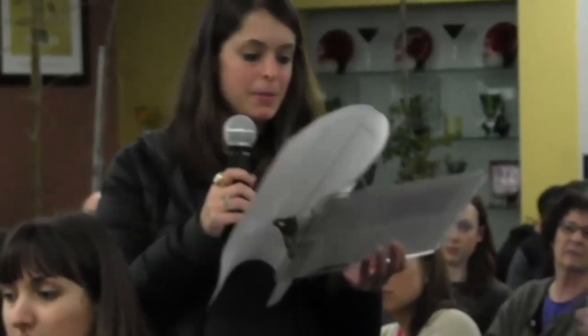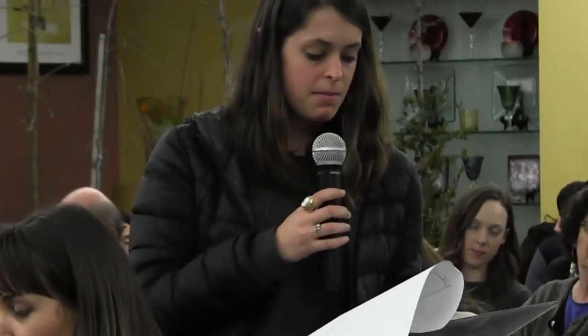Thank you, I'll try to explain what we did. We looked at the monthly demand for flushing and irrigation, and got about 32,000 gallons of water for each month if you take the maximum irrigation demand. And then we looked at the total gray water demand, which is roughly 102,000 per month. So we saw that we'd be able to supply all of our required non-potable demands with gray water. Then to get a sizing for the tank, we looked at the total demand per day.